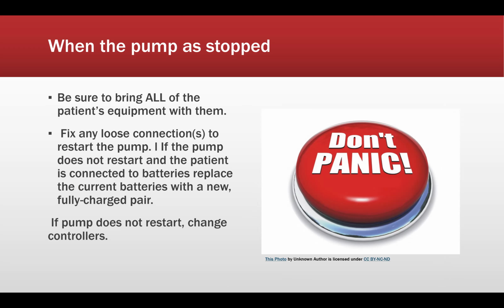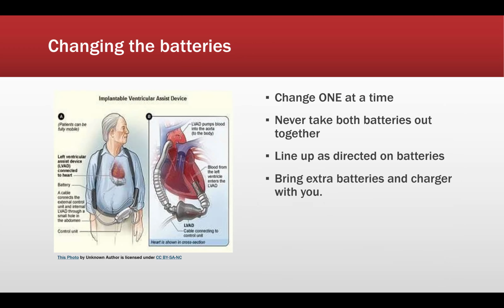If the pump does not restart, change controllers. The patient will have a spare for everything, and the controller is the unit that's on there. We can change that out as well. Again, changing the battery is a big one. Change them one at a time. Never take both batteries out together. Line them up as directed on the batteries. And again, bring the extra batteries and the charger with you.